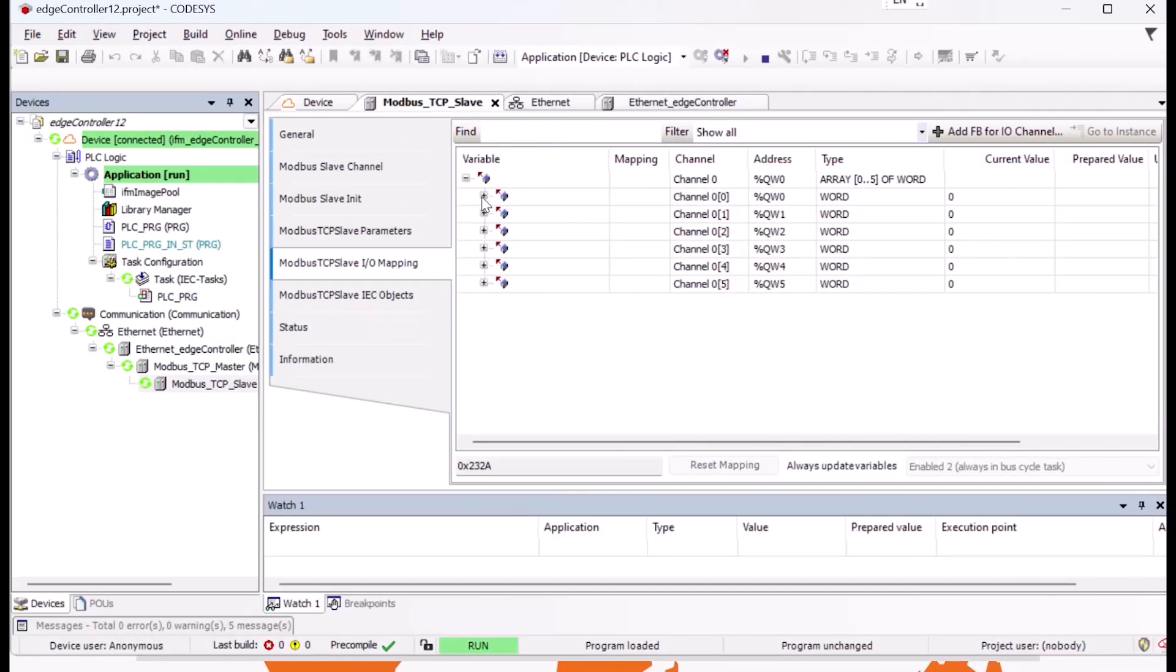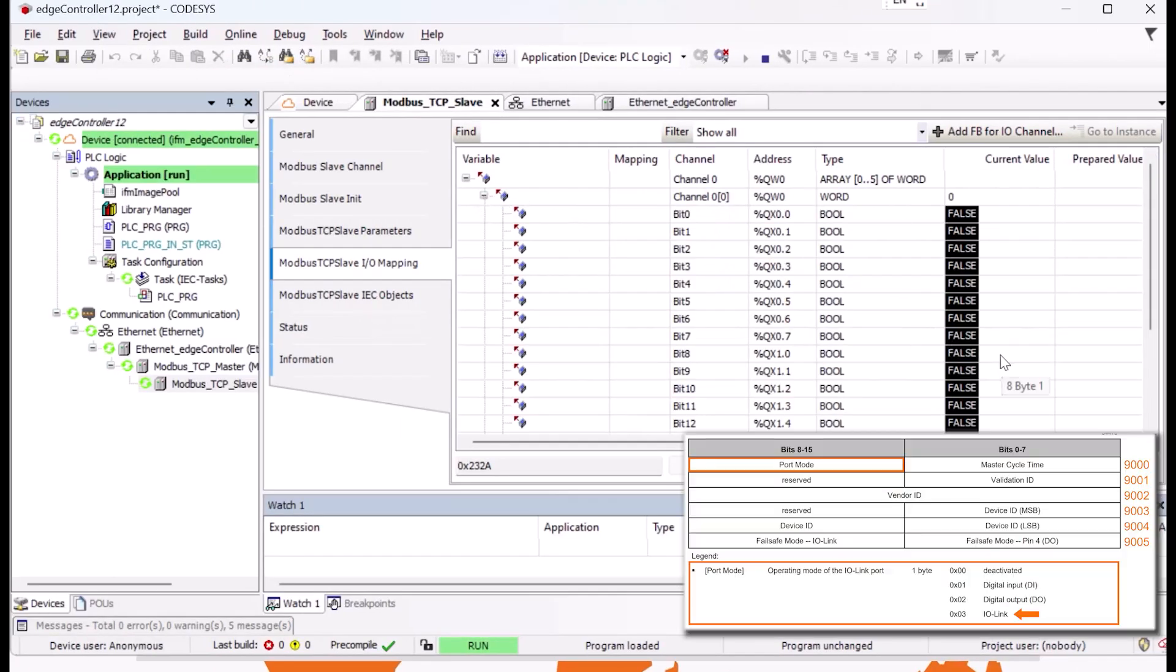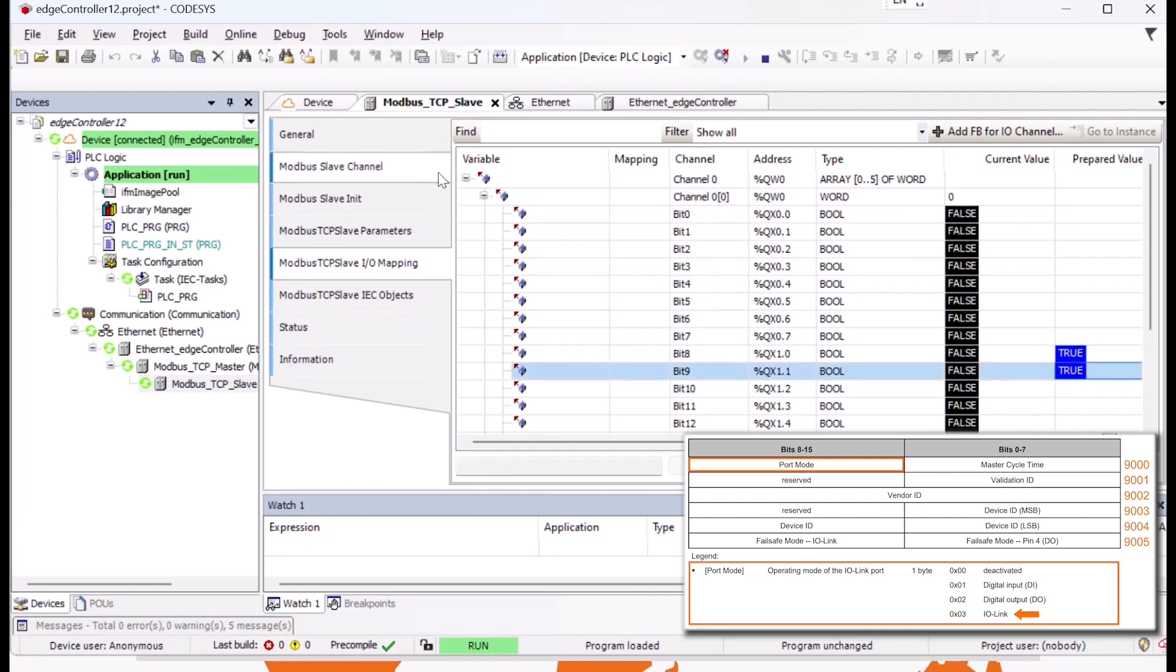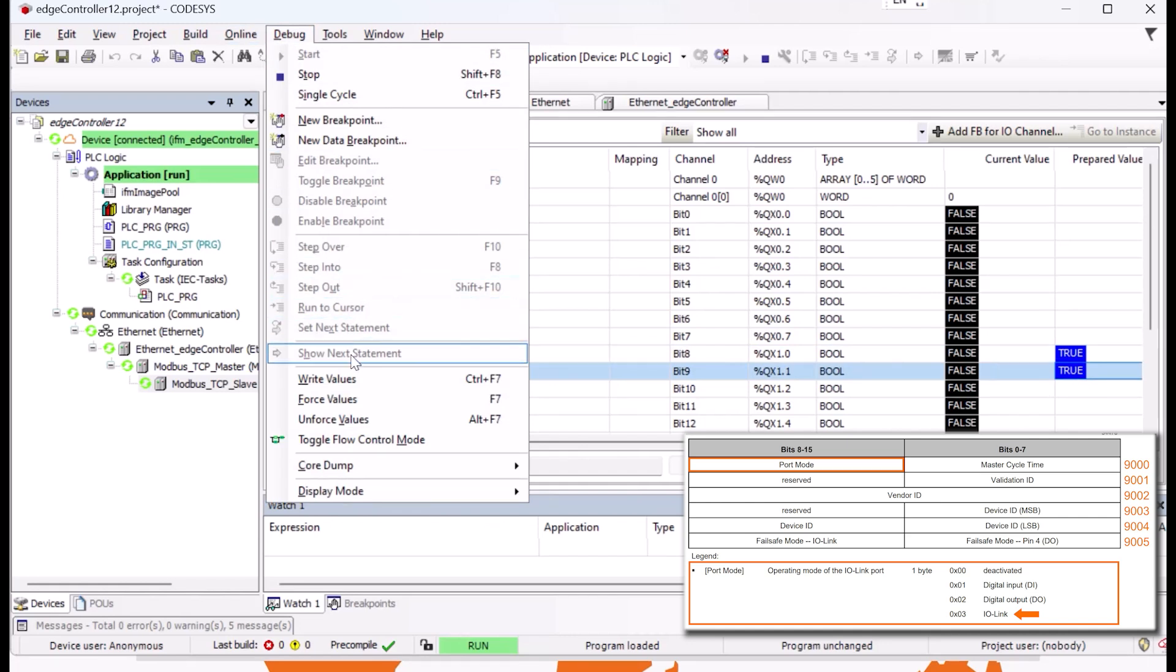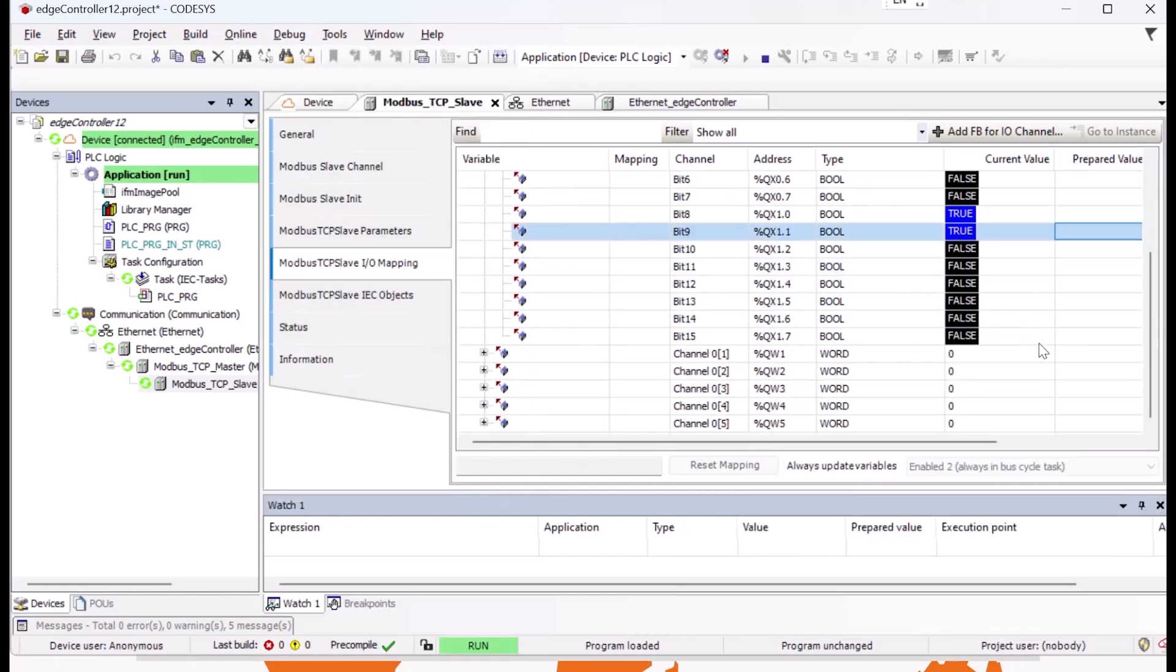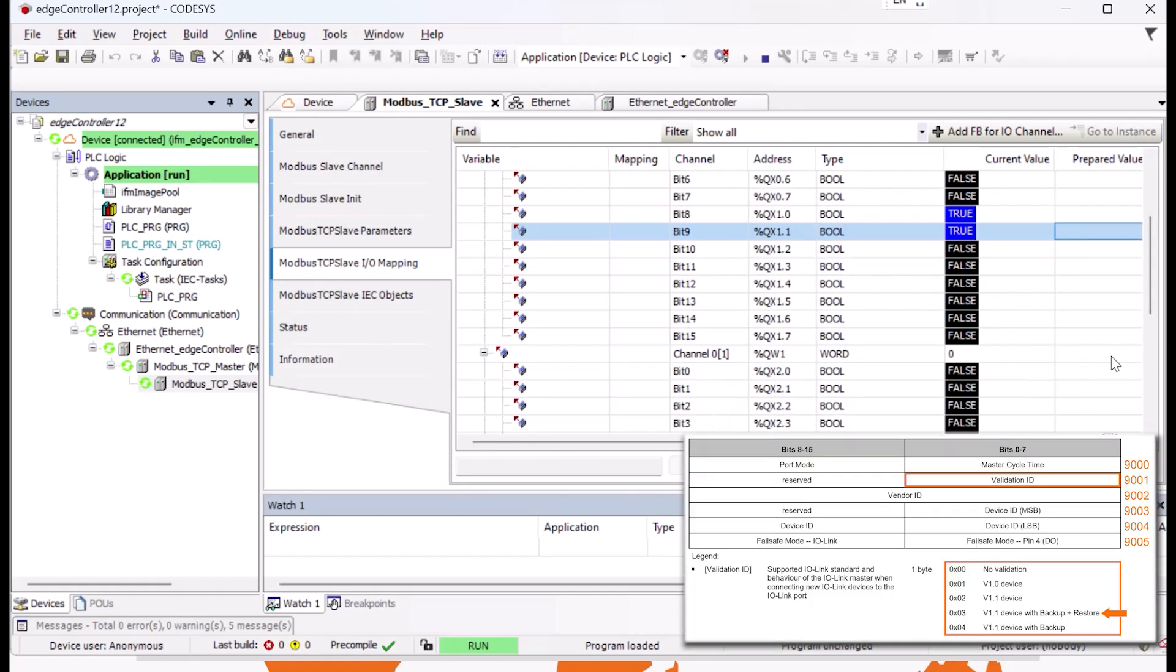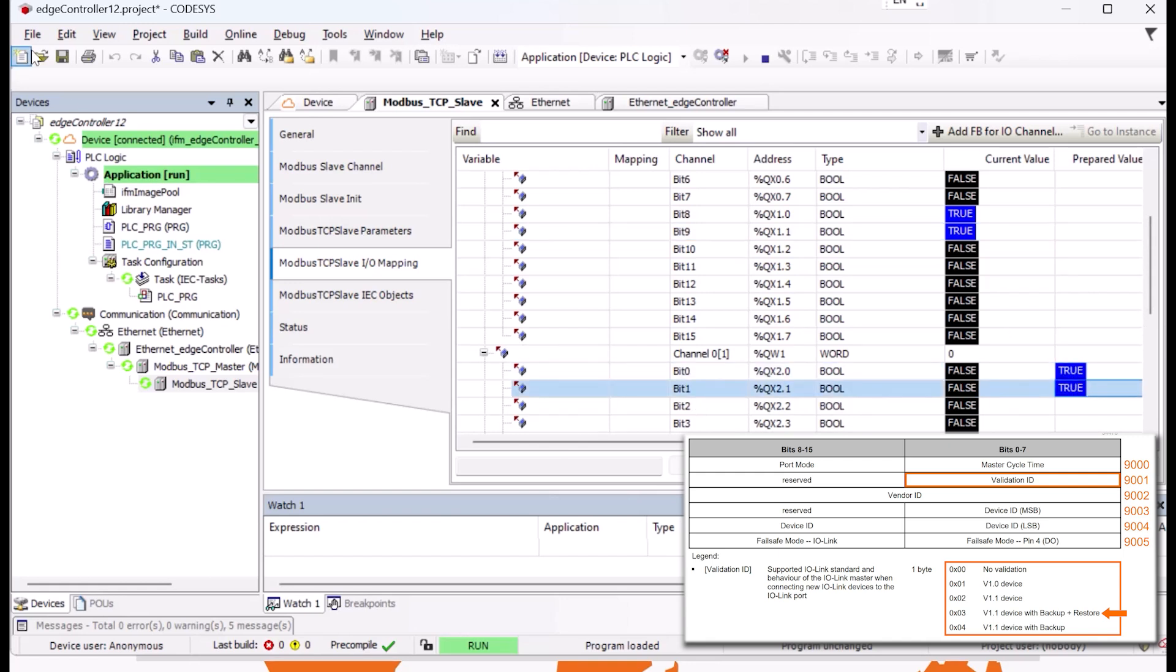Before we go on, we change both parameters in Codesys. In the IO mapping of our new created Modbus channel, we select the second byte of the Register Address 9000 to set the port mode. The same procedure is done for the first byte of the Register Address 9001, where the validation ID can be set.